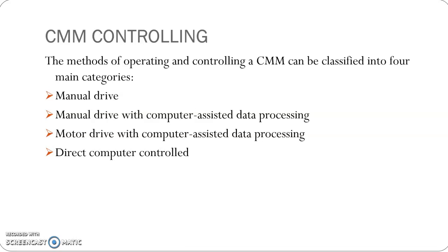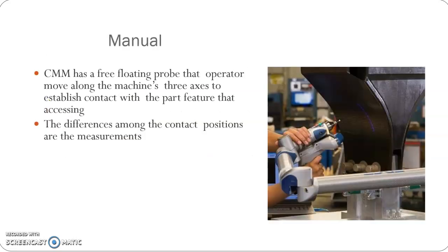The CMM controlling includes manual drive, that is purely manual drive; manual drive with computer-assisted data processing; motor drive with computer-assisted data processing; and direct computer controlled or DCC. The manual control system is the simplest one. It uses a free-floating probe that can be controlled manually by the operator's arms. The probes move from one location to another manually, and the difference among contact positions are the measurements.